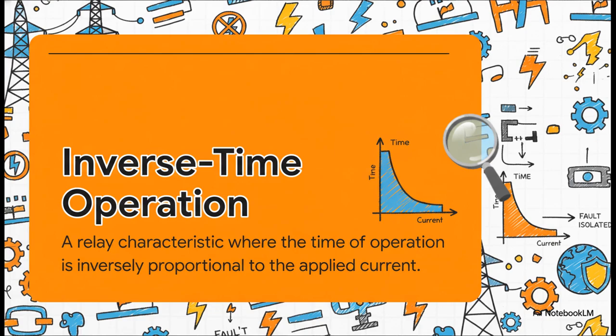The time it takes for that protective relay to act is inversely proportional to the current. So a small overcurrent might be allowed to hang around for a few seconds. But a massive, massive fault current, that's going to cause a trip almost instantly. The bigger the problem, the faster the response.